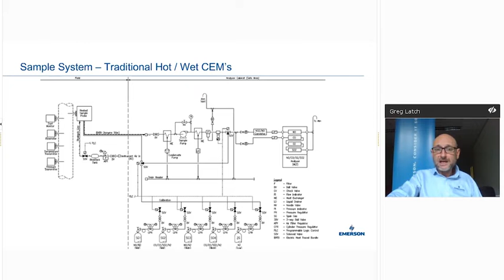Some of the downsides, just as a brief summary, as an overview for both of those systems, every time obviously you start placing components that manage your sample handling stream within the loop, you do tend to have what we call an RC network, R being restrictive, C being capacitive. So obviously now increasing your capacitive and your restrictive processes from a sample through an analysis system, your analyzers, and this will potentially create some challenges in timing. And from a process control point of view, time is your enemy. Ideally, you do want to have a very fast update time. You can manage some of those aspects, and that's through what we call fast loop processes, which we don't touch on today. But again, in the same context, you still do have to then manage that process from a wet point of view, managing those wets prior to analysis.